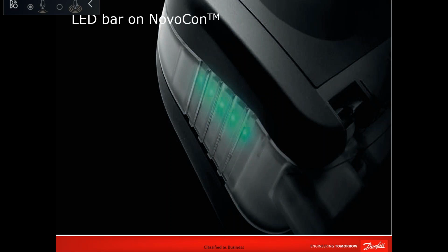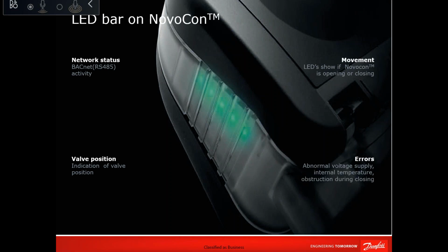That's why I'm saying, if the BMS is not yet ready and you need to boost the power, and you have your wiring done, energize the actuator. There will be one red, two green, and one off. That means that the power supply is dropping at that actuator. There is your boosting point. So that's simple. Everything, valve position, movement, and errors, can be seen from the local LEDs of the actuator.